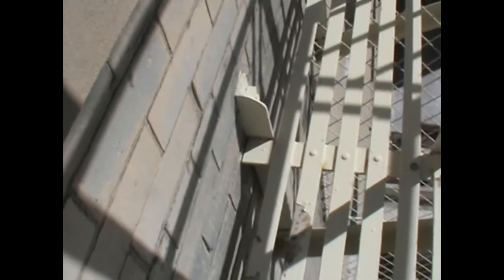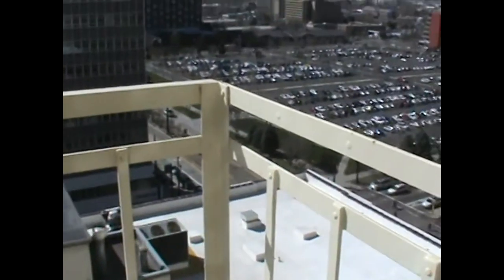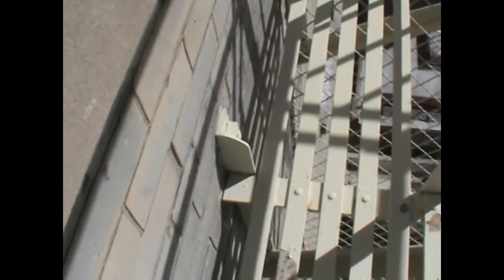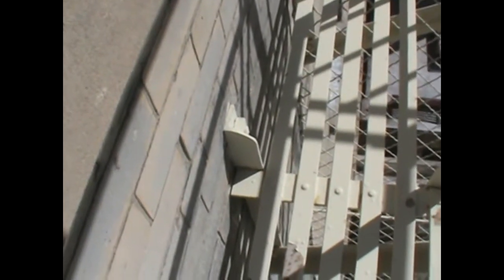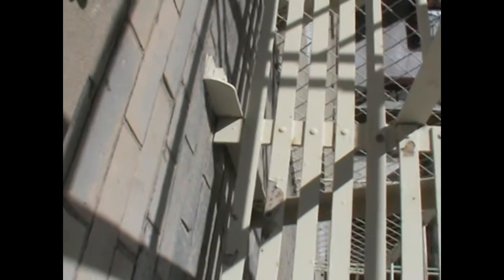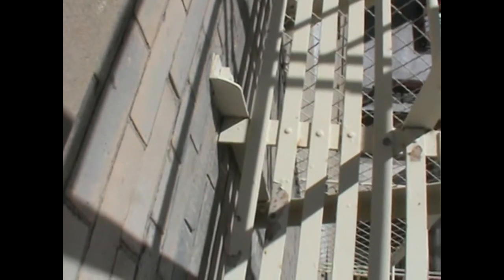That's a good question. I want to duplicate it. Update the hardware. The hardware is all external, so yes, all the major structural rivets need to be popped out, and you need new fasteners. That'll take care of your railings, your platforms, and everything, right? Okay. But then this through bolt, to not have to load test this platform, I want to keep my original through bolt, but I don't want to disturb the inside. What can I put next to that one? Keep the original. What do I put next to that we taught in class? Well, let's see, it was another through bolt, epoxy or through bolt.